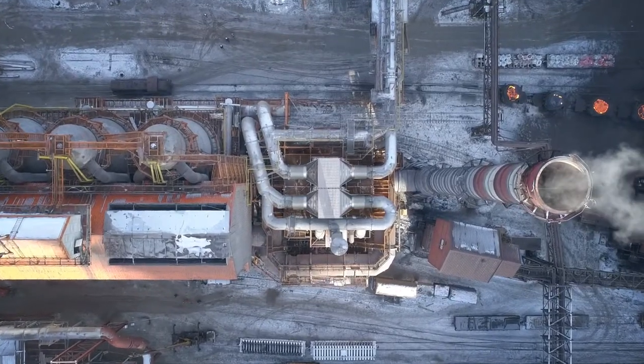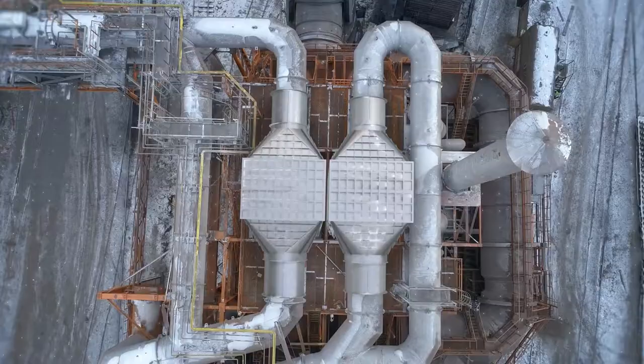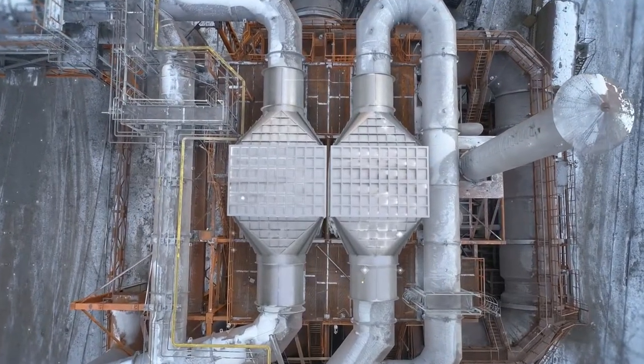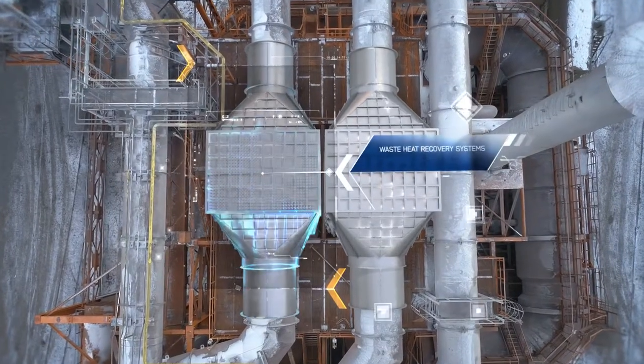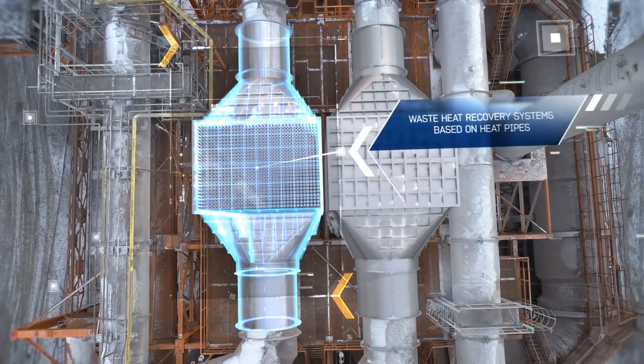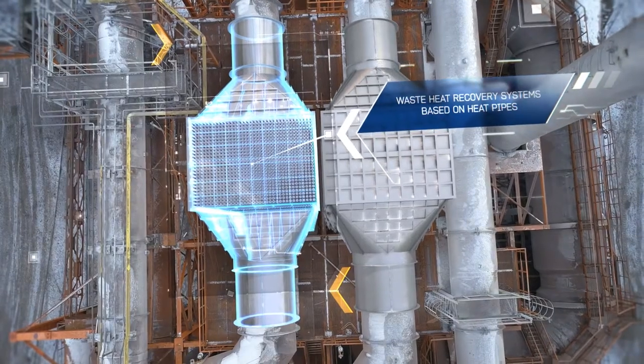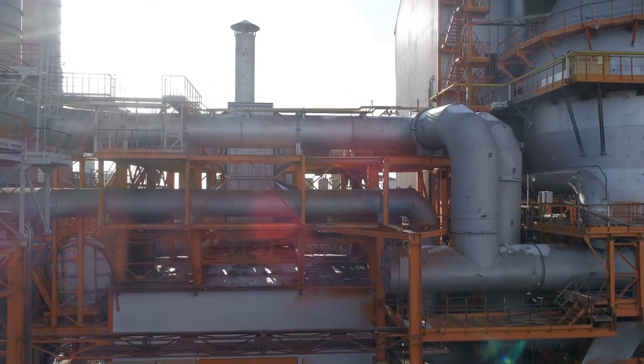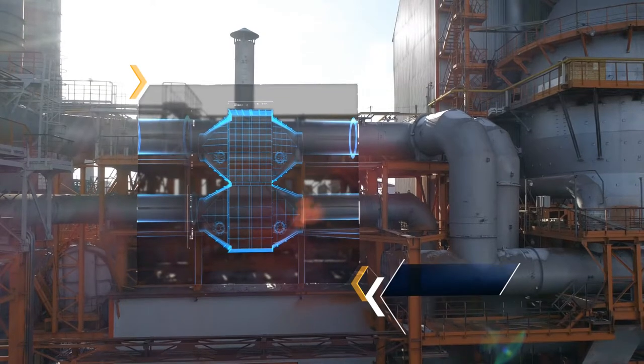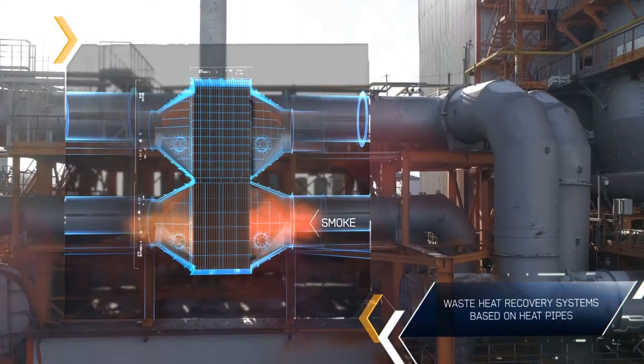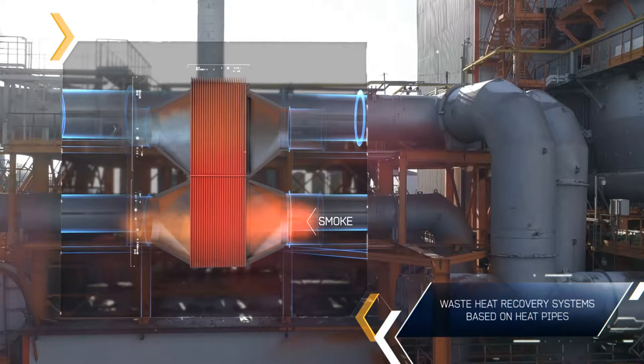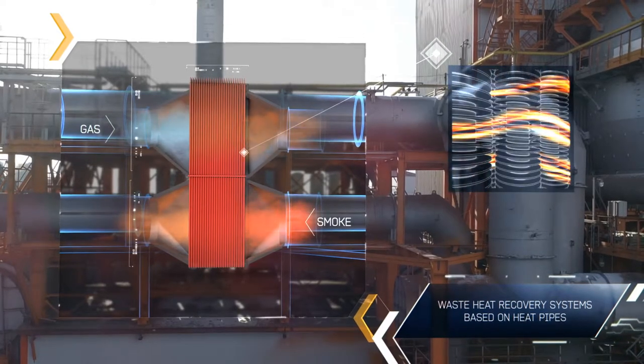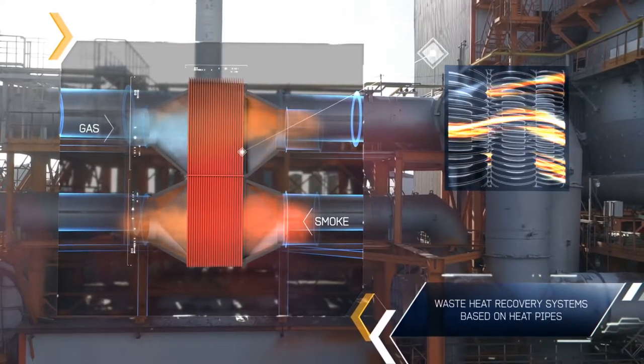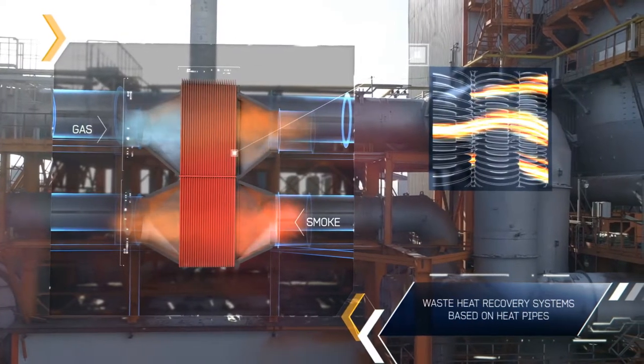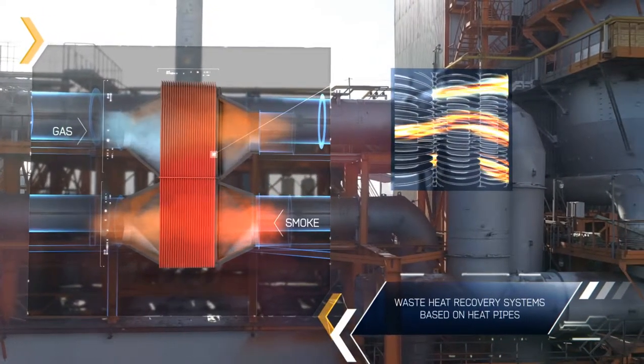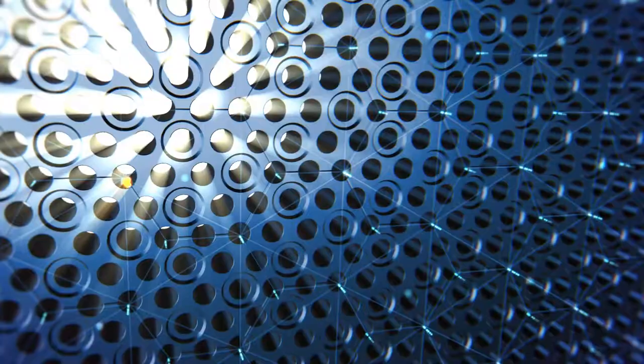Nowadays, the heat exchanger design based on heat pipes is the most popular design of the waste heat recovery system developed by Kalugin's engineers. All the designs of the waste heat recovery system are of general purpose. They can be efficiently used in the iron and steel industry, heat and electric power industry, machine building industry, construction material production, chemical and petrochemical industry, and in all industries where low-grade waste gases with a temperature up to 300 degrees Celsius are available.